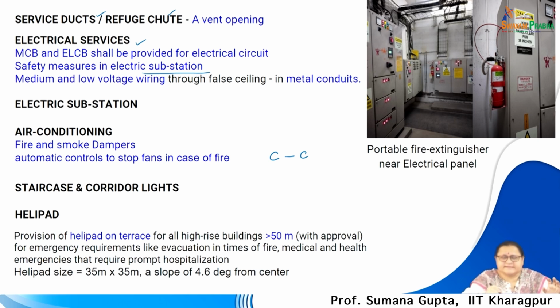Staircases and corridor lights should all be connected to emergency lighting. As we have seen in general buildings, it may not be supported with an electrical connection to the emergency supply, but in this case, because it is a tall building or a high rise building, the staircase and corridor light should be supported with the emergency supply.